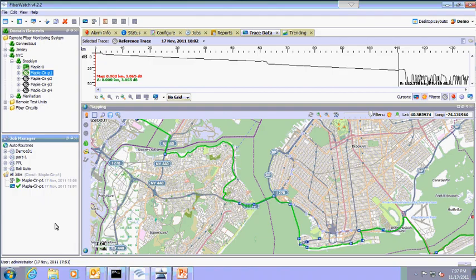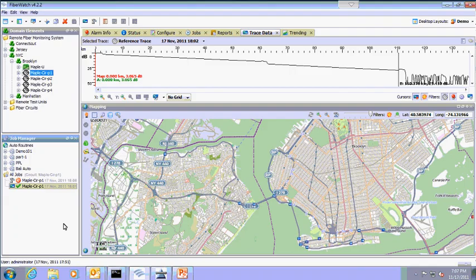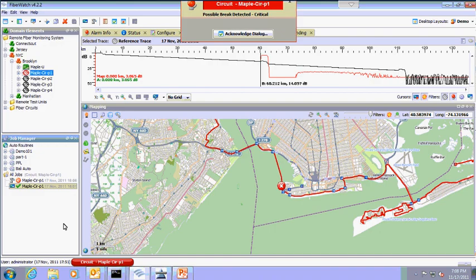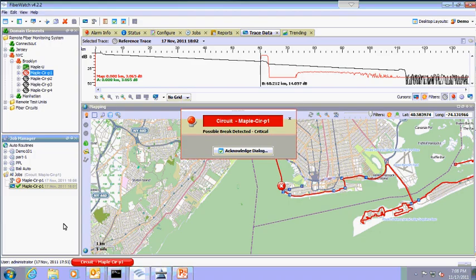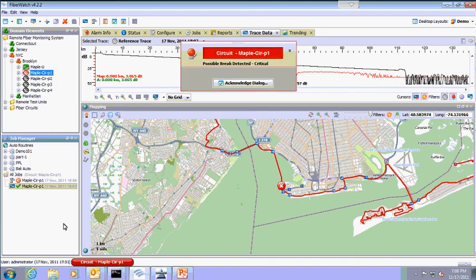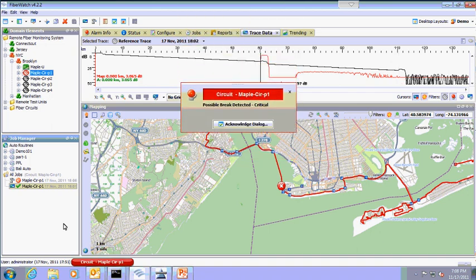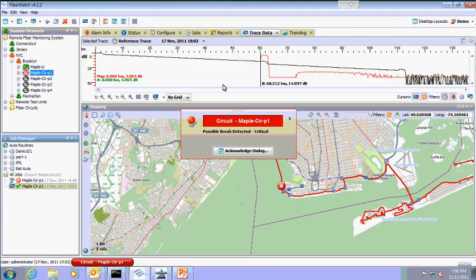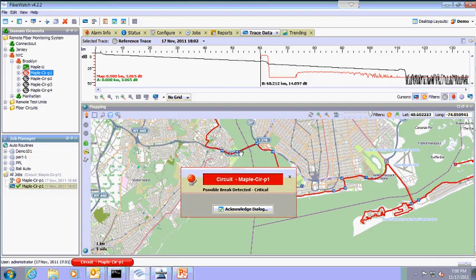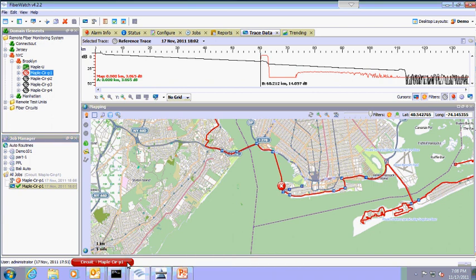The route icon and route on the map will turn from green to red. FiberWatch has identified that there is a break and will update the real-time trace with the break at 60.2 kilometers. The route icon is now red and the new trace is red since the deviation from the reference trace has passed the preset threshold. An alarm is automatically generated and automatically appears on the operator's screen.